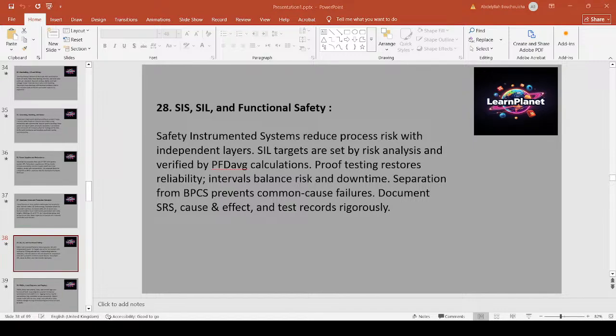Safety instrumented systems are independent layers to reduce risk. SIL levels 1 to 4 correspond to reliability targets determined by risk analysis. Define SRS, cause and effect, and proof test intervals that balance risk reduction and maintenance downtime. Proof testing and spares planning are part of maintaining the achieved SIL. Ensure physical separation from BPCS to avoid common cause failures and document all testing. Example: an emergency shutdown valve with SIL 2 requires redundant solenoids and periodic proof tests recorded in the safety management system.